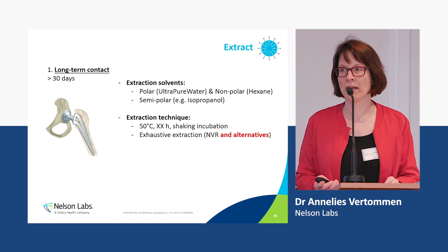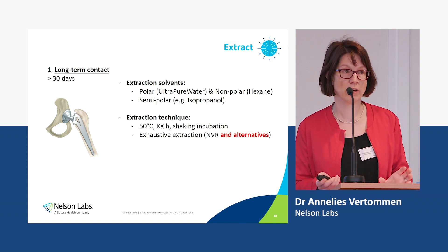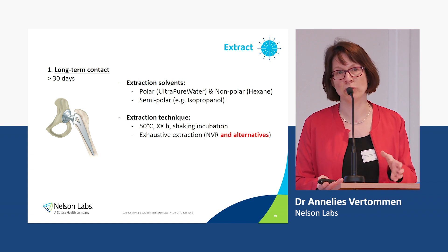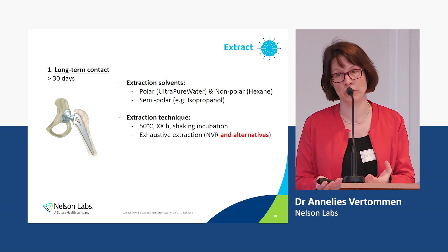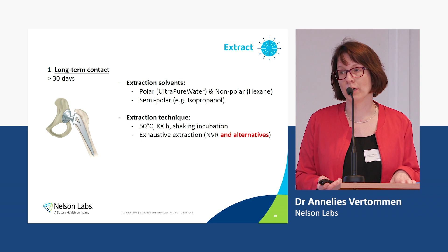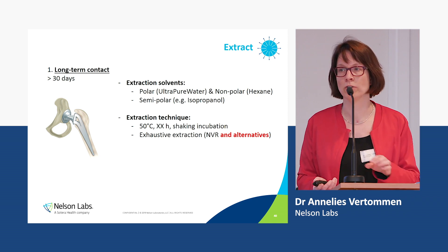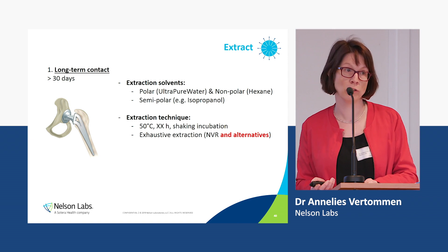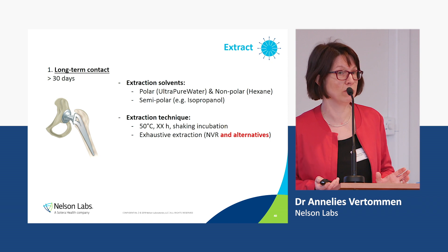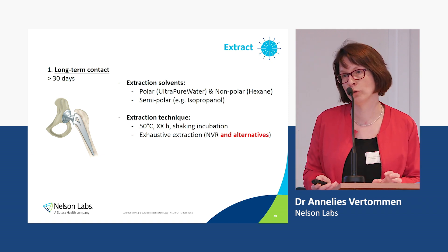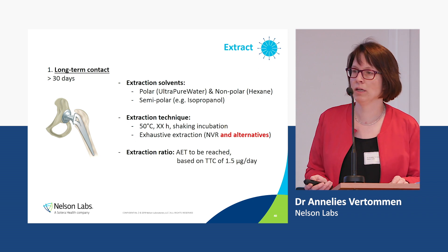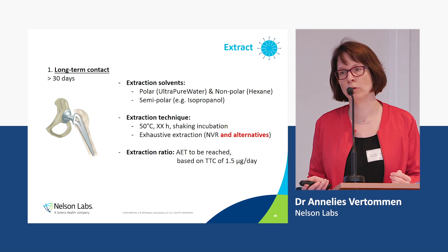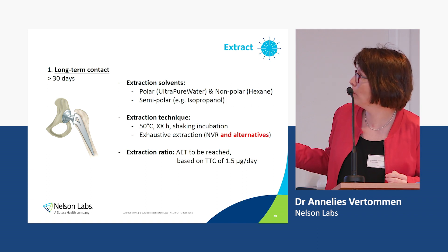The extraction technique for long-term contact devices is exhaustive extraction — meaning you need to prove that you extract all possible chemical compounds that can come off your material using this technique. Previously, it was recommended to use NVR (non-volatile residue) for determination of exhaustiveness. Now there are discussions and alternative techniques that also give you more freedom to demonstrate exhaustiveness. For devices with long-term contact, you need to use exhaustive extraction, and the amount of sample and extraction ratio are based on the TTC of 1.5 micrograms per day.